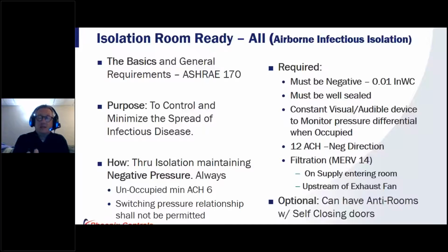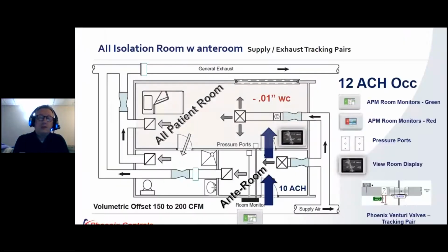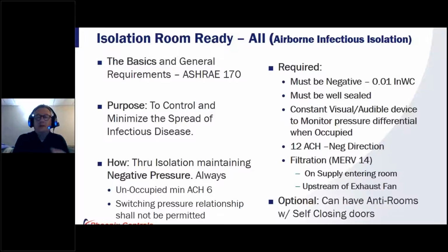They are required, like I said, to maintain negative 0.01 inches of water column. They must be sealed pretty well. And here's a code requirement that typically gets interpreted a little bit differently, and that is the constant visual audible device, right? The monitoring of the pressure differential. Now, this can be done through the BMS, but many hospital campuses are fairly large, right? And so it's more important for the staff and the people working in the hospital or that space to understand that that space is pulling a negative draw always, right? So constant local pressure monitoring is certainly key for these spaces.